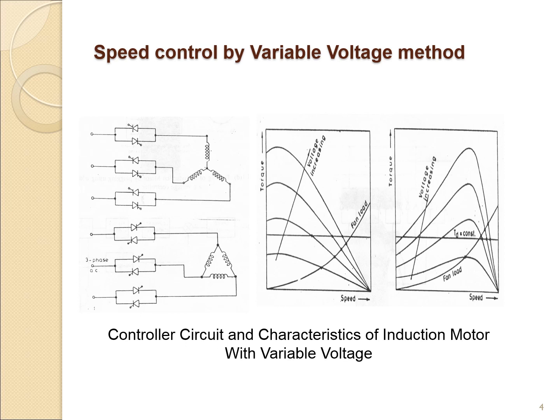Speed control by variable voltage method uses an AC voltage controller. This is a three-phase AC motor; the three-phase AC voltage controller output is given to the AC motor. By varying the firing angle of the AC voltage controller — which has two SCRs connected in anti-parallel direction — the output voltage can be varied.